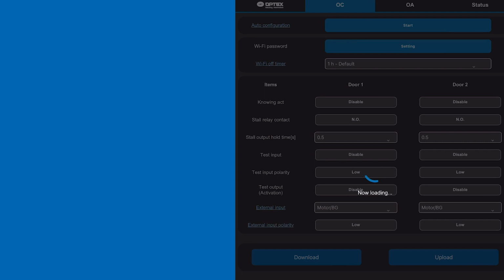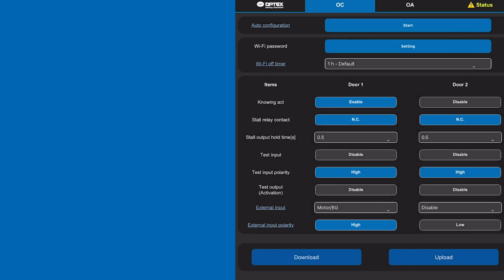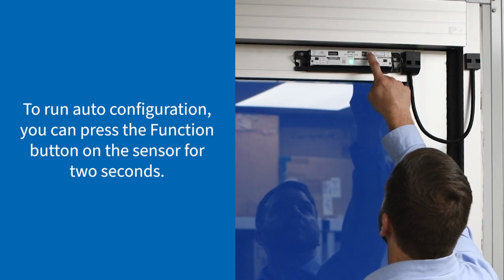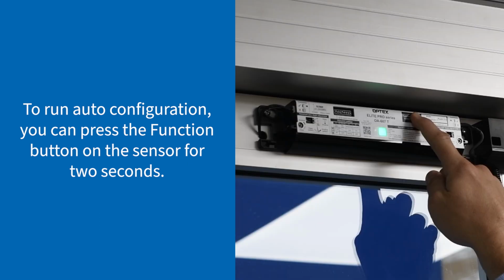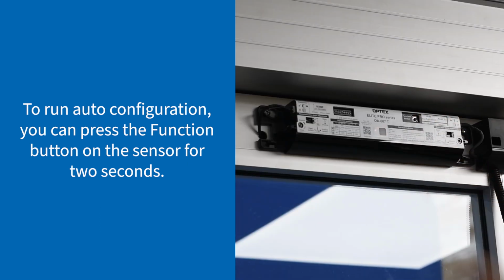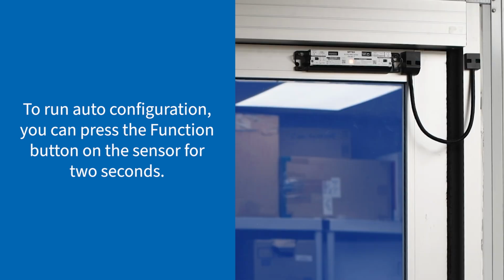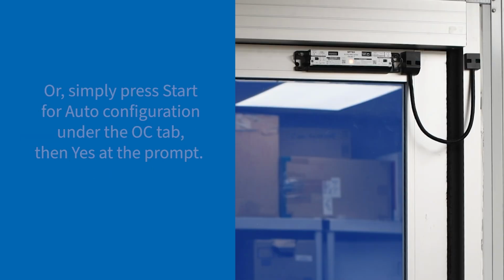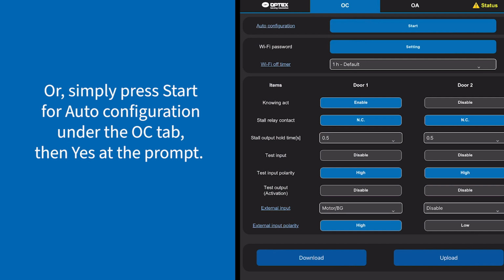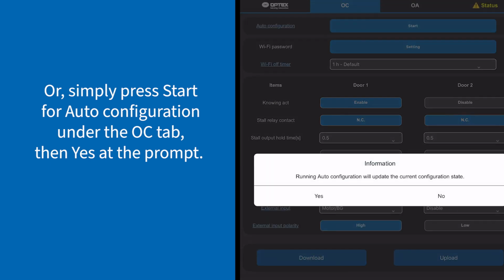Under the OC tab, there are settings for basic configuration. To run auto configuration, you can press the function button on the sensor for 2 seconds. Or simply press Start for auto configuration under the OC tab. Then Yes at the prompt.